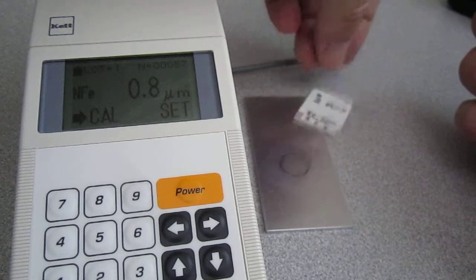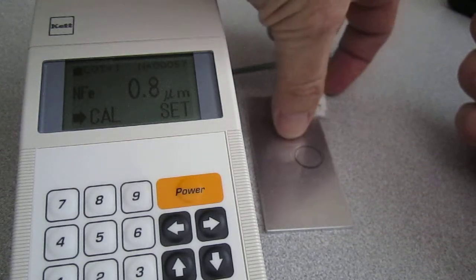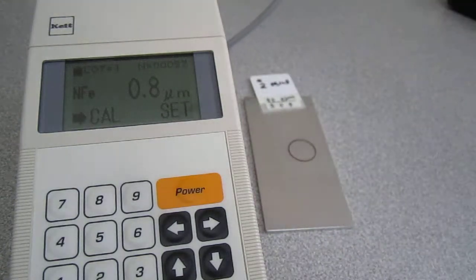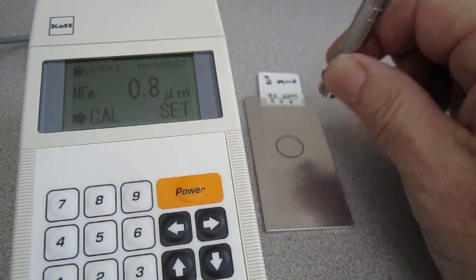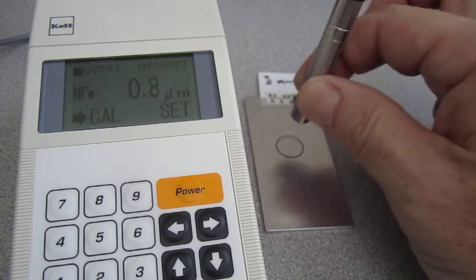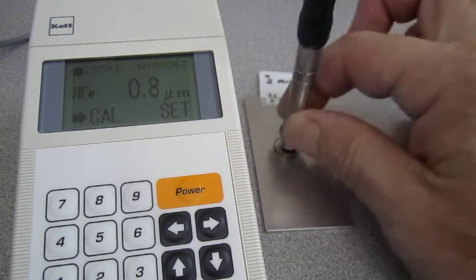Now, normal application, you wouldn't want to measure on a bare substrate. What you'd want to measure is with some sort of film thickness, coated, painted, plated, or whatever. In this case, we're using one of our shims that we use to calibrate the instrument.